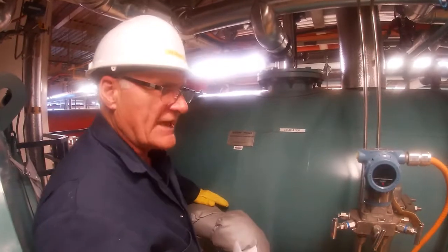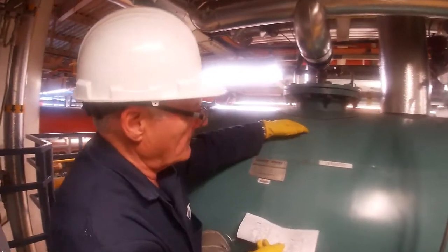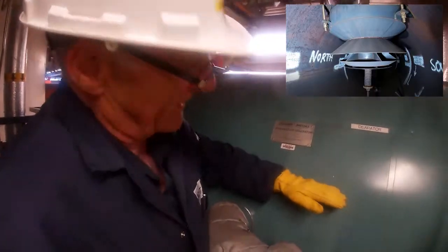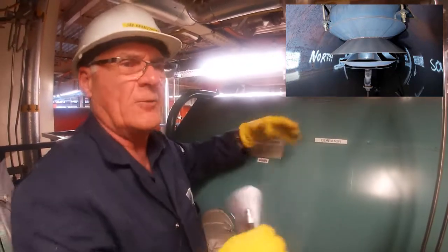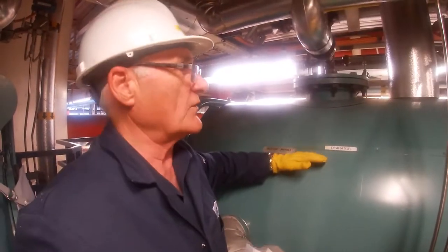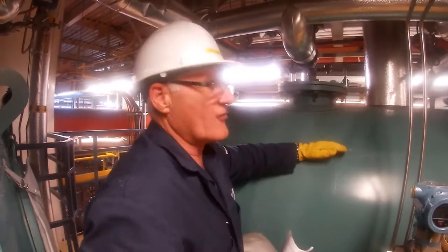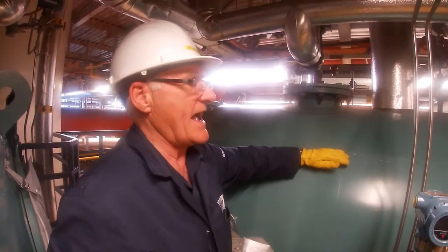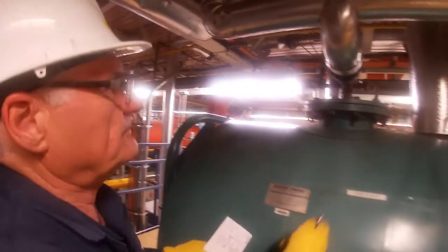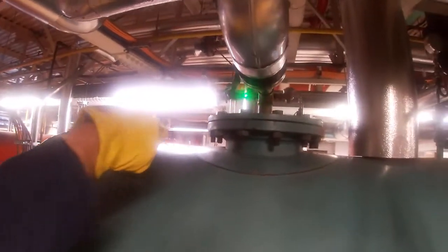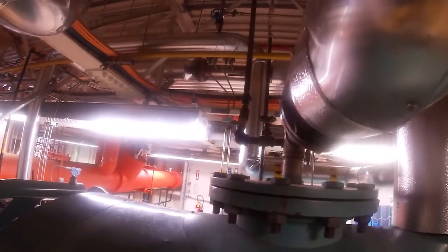So this is the maximum level it can get to, because the spray nozzle, which you'll see on another video, is down to about here, and it's bringing the water in and it's spraying and separating, and that helps the deaeration process. And so the deaerated water sits in the bottom. The air that was in the condensate that came back, or the fresh water that comes in, will actually collect in the top, and there's a vent line right there, and there's a valve that we've got to open a little bit later, and that vents out to the roof.